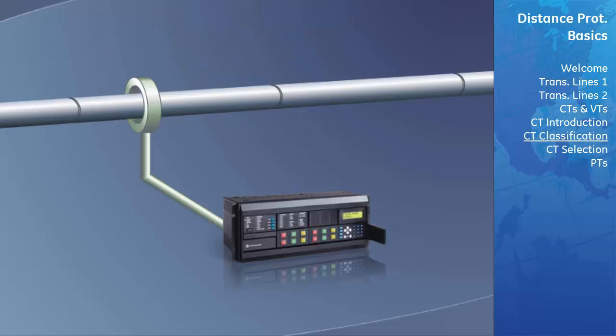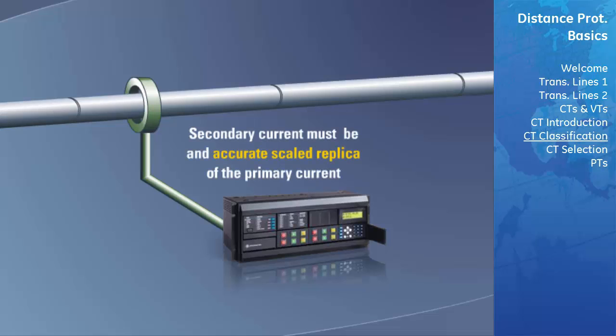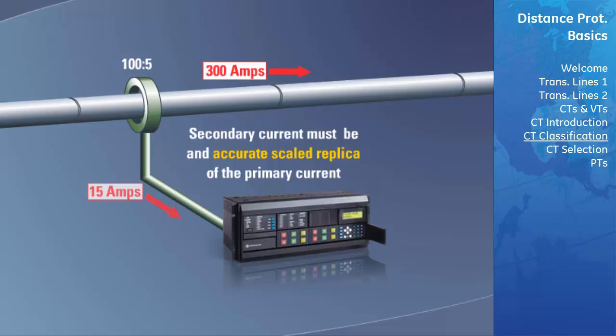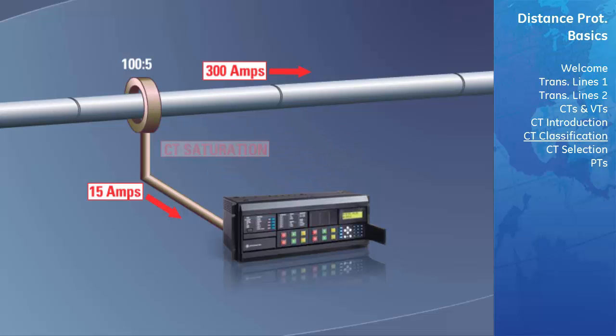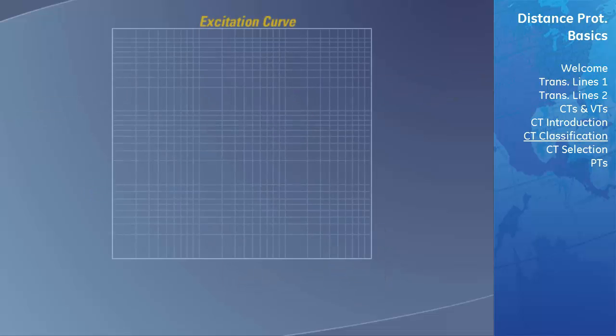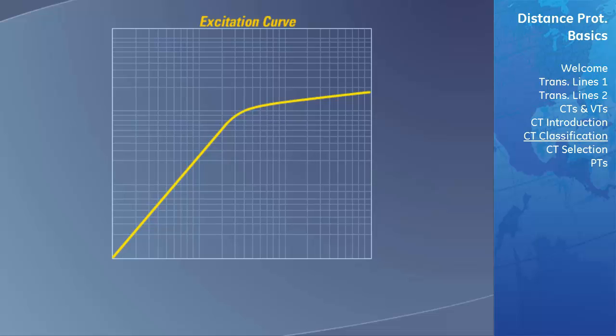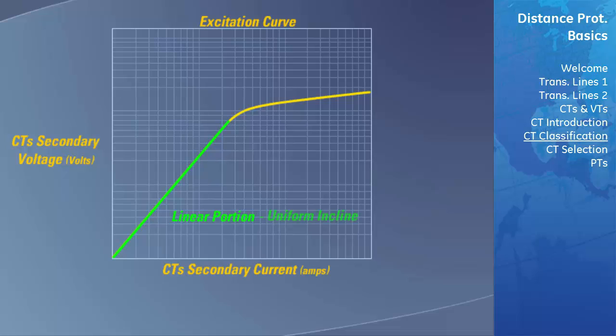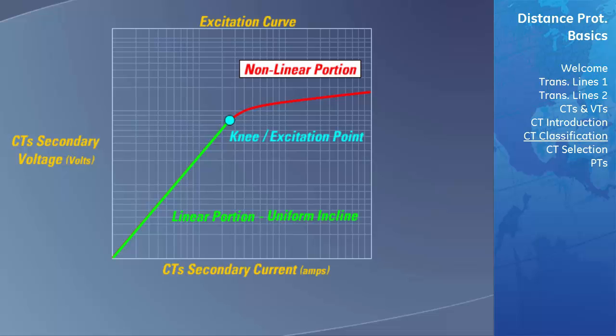In order for the relay's measurements to be accurate, the secondary current from the CT must be an accurate scaled replica of the primary current. CT saturation occurs when a current that is too large for the CT rating is passed through the CT. CT saturation can be explained using a graph displaying the relationship between secondary current and secondary voltage applied to the relay's terminals. While in the linear portion, the current and voltage rise at a uniform rate. When they rise above the linear portion of the curve, their relationship is no longer linear — the current increases at an exponential rate greater than the voltage. The point where they stop relating linearly is known as the knee or excitation point.